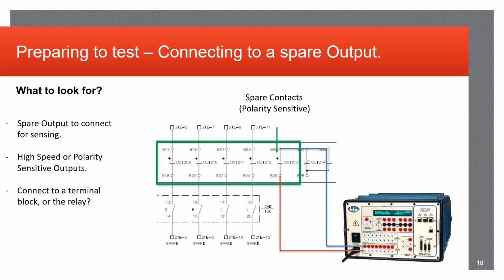It's easy to use because it's not going to be utilized for any other function other than what you're going to be implementing yourself. It's also going to be polarity sensitive sometimes, so you'll want to watch out for that and make sure that you got it all set up. And like I said, sometimes these spare outputs can actually go to a knife blade and nothing else. It'll just go down to the knife blade and can be even easier to connect to rather than going to the back of the relay cabinet.